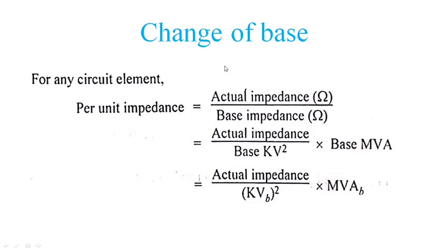So you have to find the per unit reactance network or impedance network of a given power system network for those new given base values. That means the base values are changing. While changing these base values, the per unit values of each equipment connected in the network also change. That change in per unit value of each equipment, or the new per unit value of each equipment, can be calculated by using the following final formula.